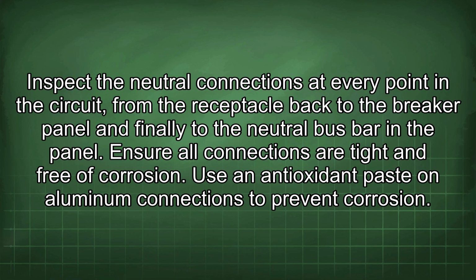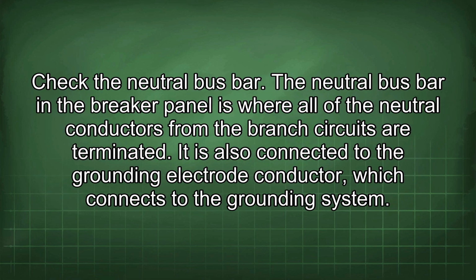Ensure all connections are tight and free of corrosion. Use an antioxidant paste on aluminum connections to prevent corrosion. Check the neutral bus bar. The neutral bus bar in the breaker panel is where all of the neutral conductors from the branch circuits are terminated. It is also connected to the grounding electrode conductor, which connects to the grounding system.